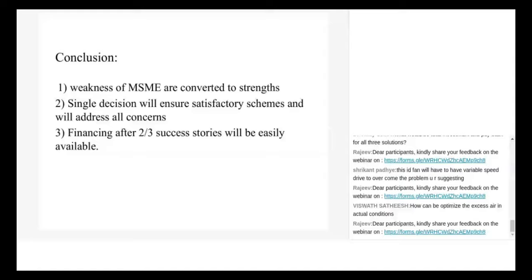And in the initial period, when volatiles come off, you require a very high amount of air. Since the surface area is limited, if you tell him to cut down on air and optimize this, he will just say, okay, come on, do it. And then there is a problem, because you cannot have a VFD programmed after every firing in a way that initially there is high air and then it starts going down, because air also does two or three jobs in this.